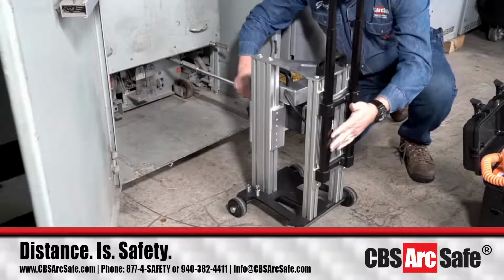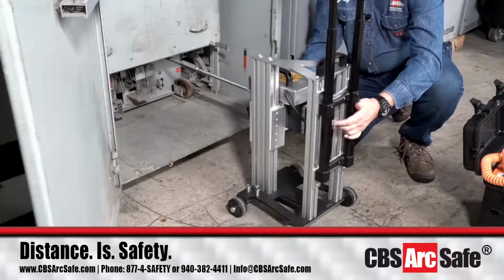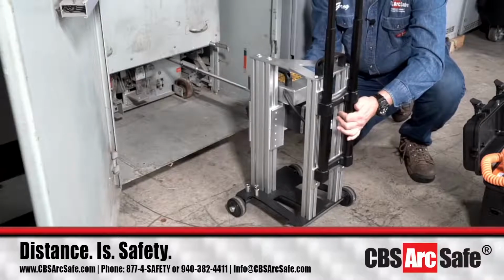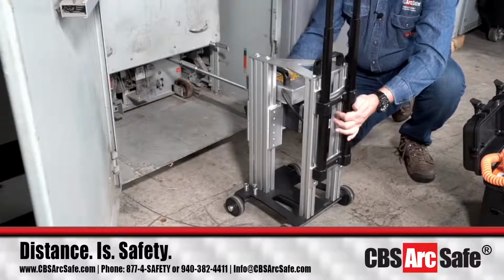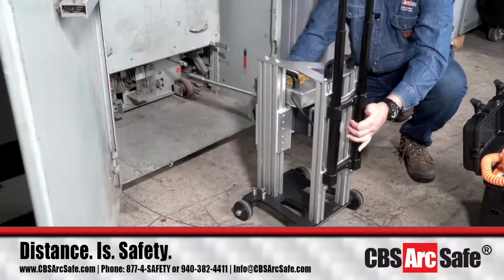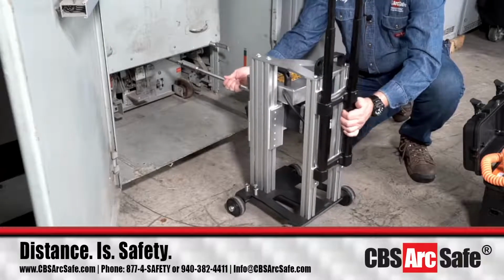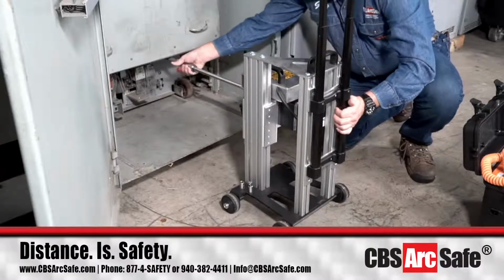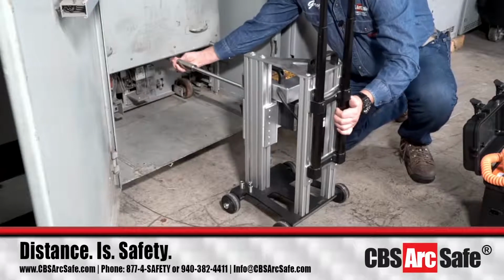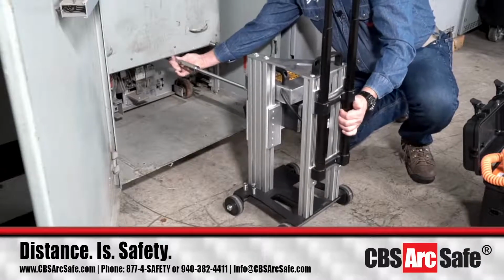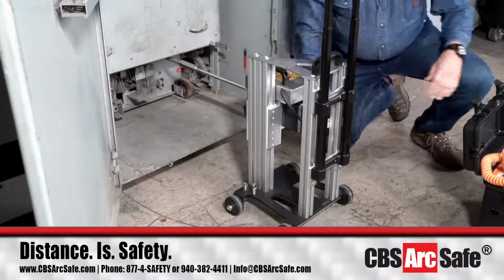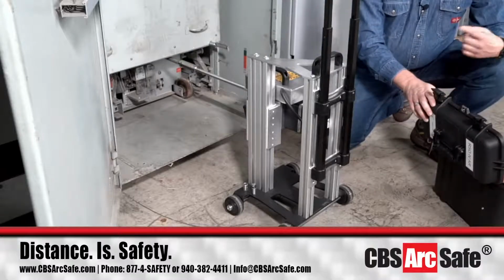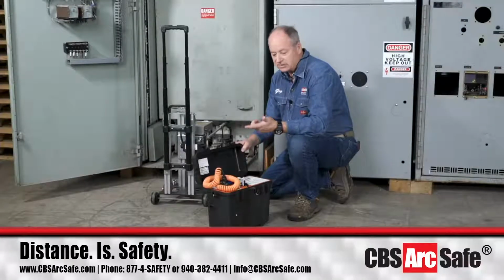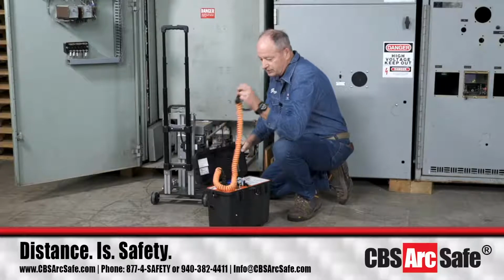Some things about a DHP breaker you may not know if you're not familiar with it: this breaker free spins going in and going out. So when it goes all the way in, it doesn't really reach a torque limit, so to speak, and it doesn't do the same when it comes out either. So it'll just go click, click, click, and that's the end of the racking operation.